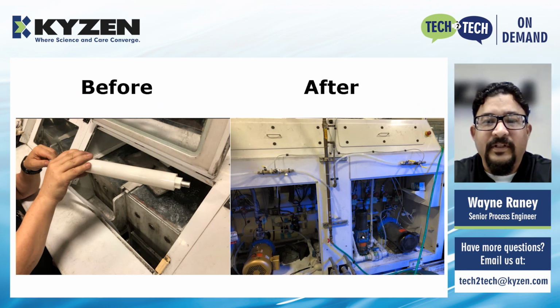So instead of a probe dipped in a tank as shown in the picture on the left, we mounted the probes directly on the output of the wash pump and directly on the output of the rinse pump in a location easy for maintenance. The picture to the right shows the new setup and location. This helps with proper measurement of the chemistry spraying directly on the parts instead of measuring a possible unmixed area in the tank.